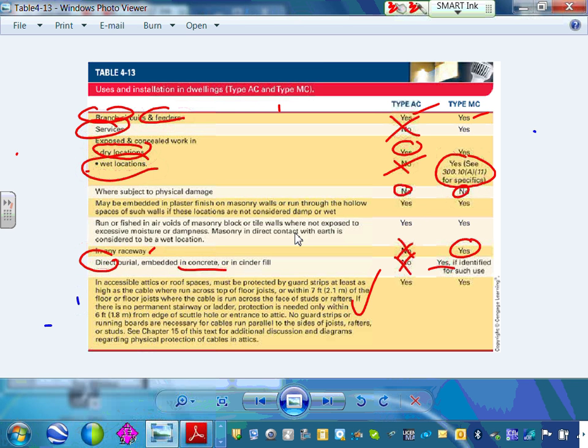We're using conduits. Then from the box, you can use this cable or that cable, MC or AC cable. MC cable, guys, between the boxes and the devices. So if you go in this wall, you take your home run into a box, and typically from the box you take an MC cable, drop through the wall, pick up this, drop through the wall, pick up the other one. Can you also drop with these? Yes, you can, but the cheapest installation, the home run for these are in between.